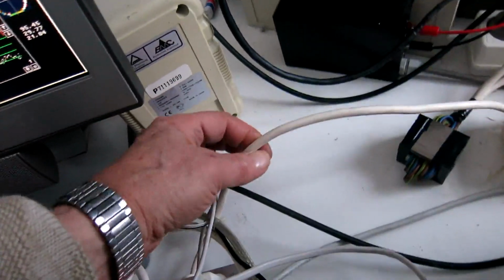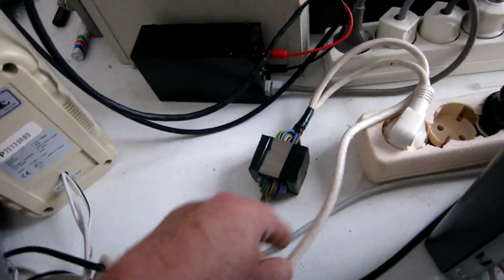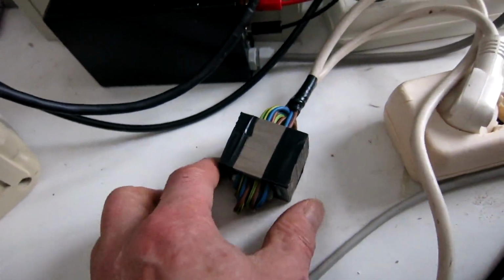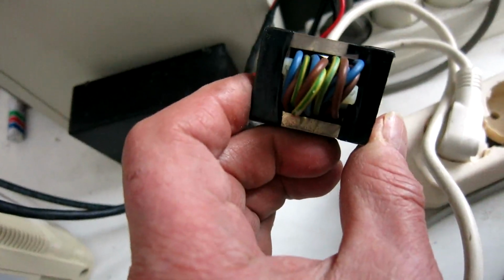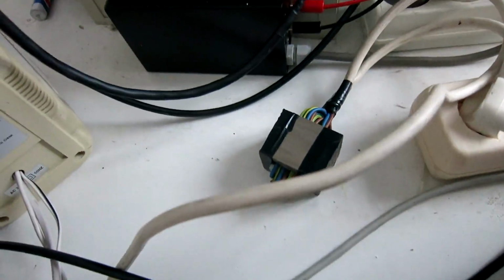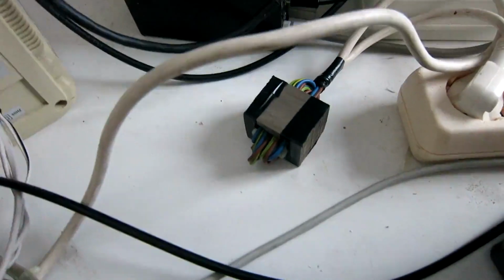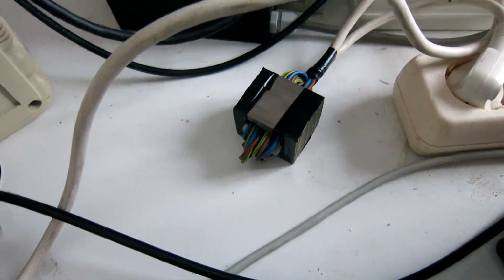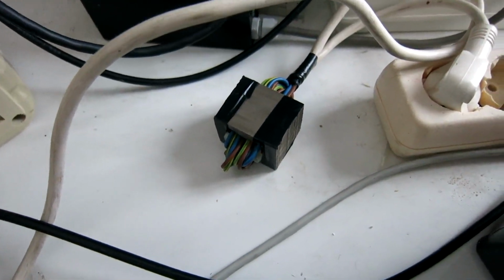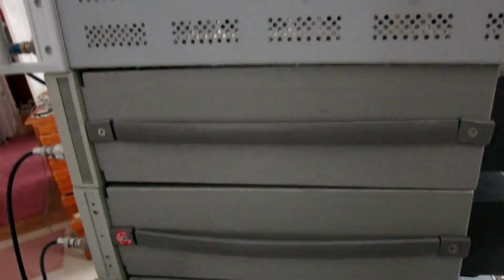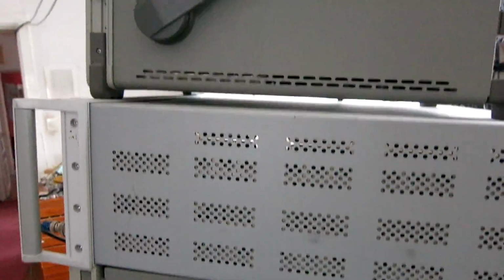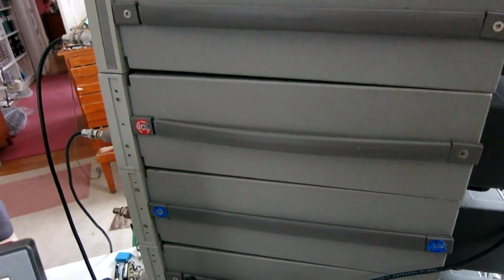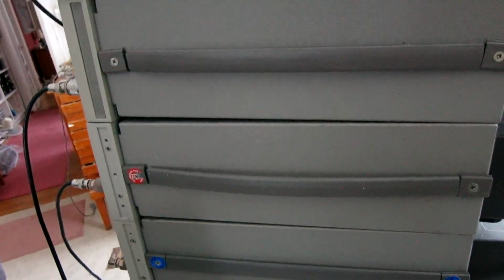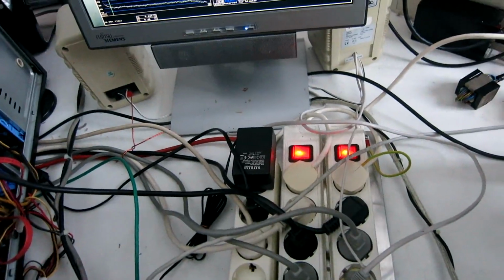Mains comes through this cable and is routed through this thing, which is a common mode choke made of mu metal, very high permeability, so it has good attenuation for common mode 50 Hz. That is to isolate the RF instruments - signal generators, network analyzer, and spectrum analyzer - so I can connect cables to this without having ground loops from this star ground.